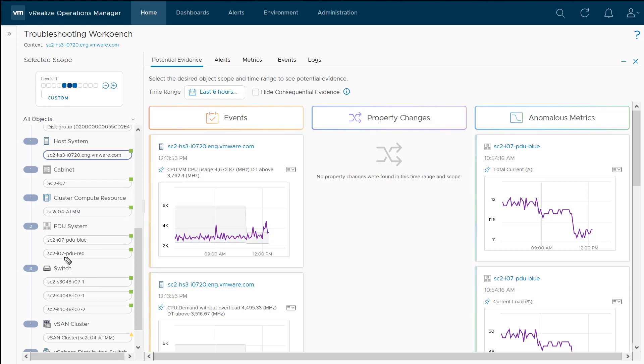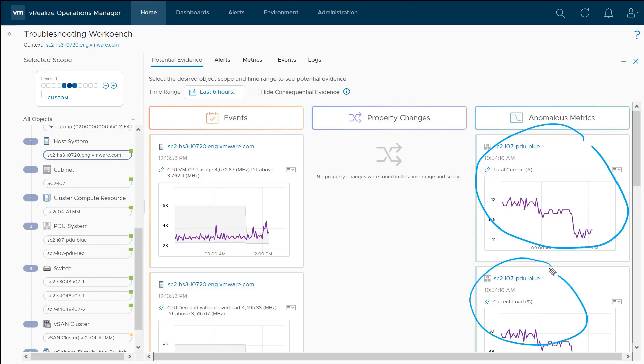Over on the right hand side, we can see some anomalous metrics. For this particular PDU, we've seen a significant drop in the number of amps that are being drawn on it. Chances are something got unplugged from this rack, but you can see how this could be useful. For example, if all of a sudden my temperatures in the data center started spiking, I might start to see CPU throttling, which would cause performance issues.